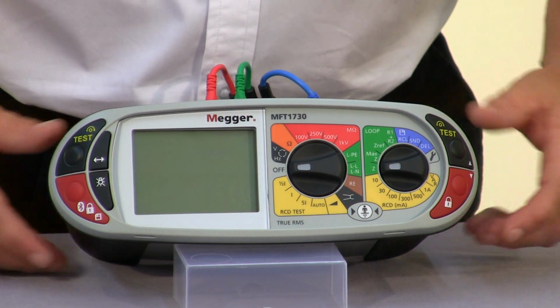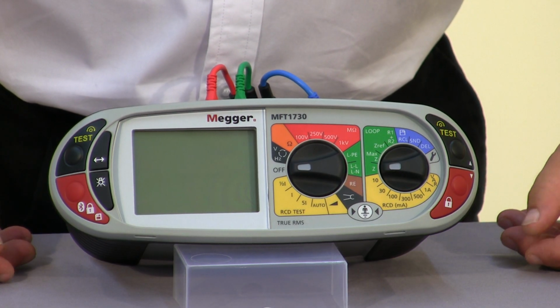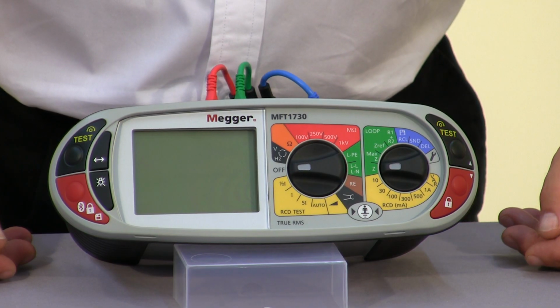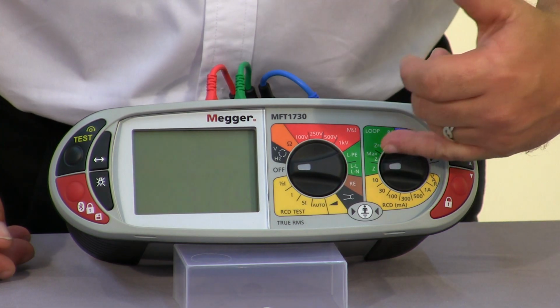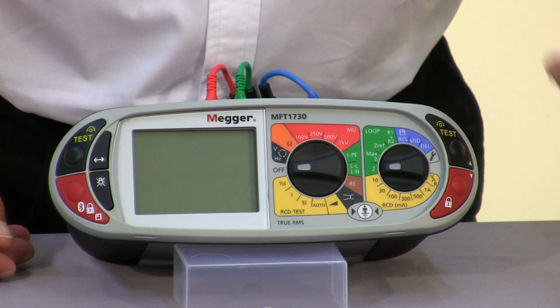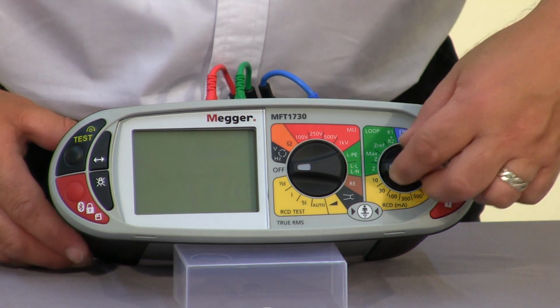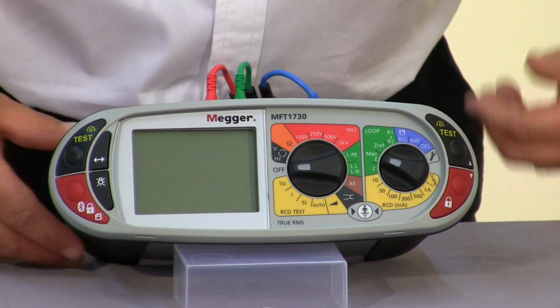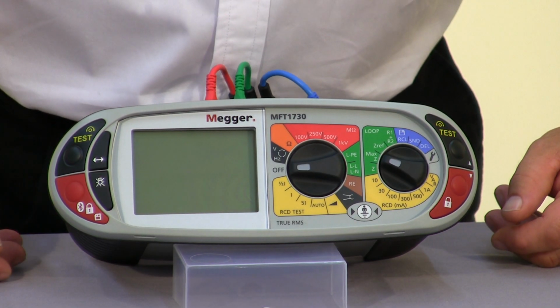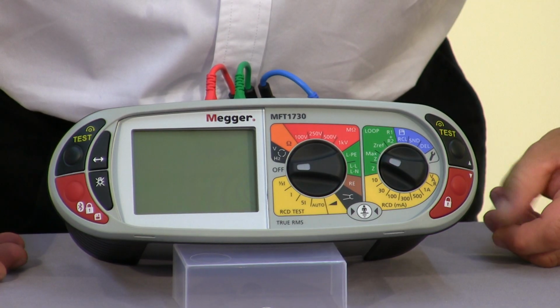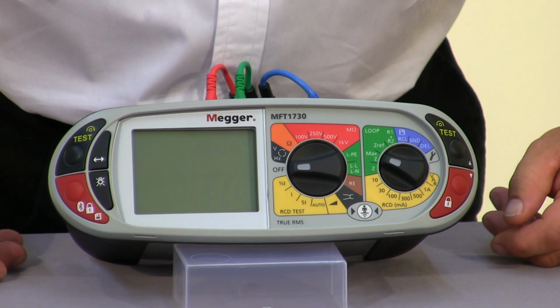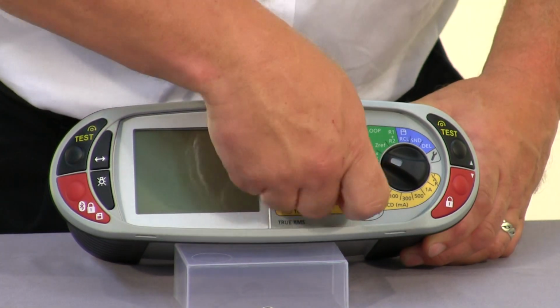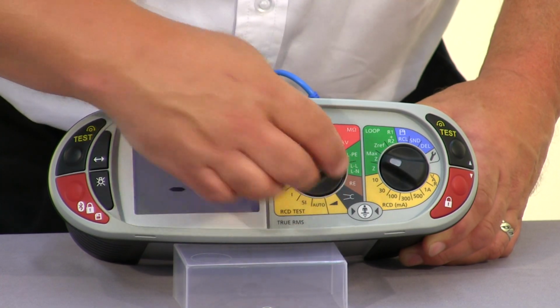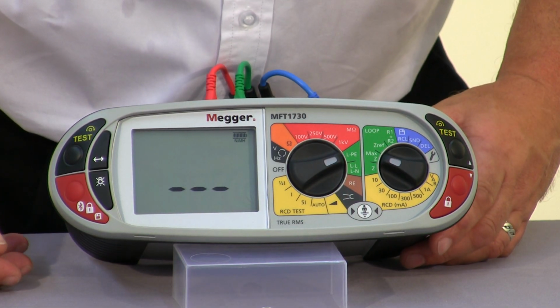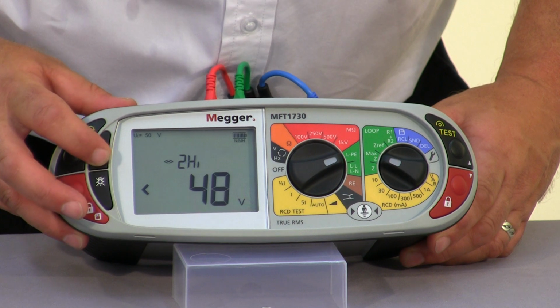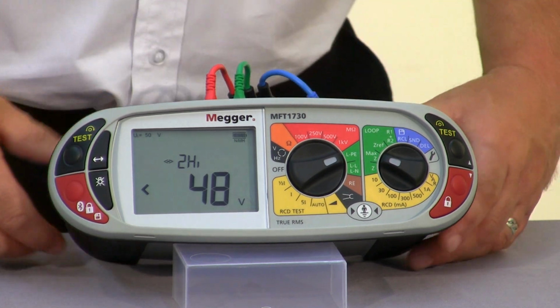Okay, so let's look at the other features that are available for loop impedance testing on the 1720 and the 1730. You'll see we have a ZMAX, a reference and an R1, R2 facility. Selecting the ZMAX first, this will allow us to carry out a sequence of tests whereby the highest reading is always returned on the upper of the two parameters on the display. So I'm just going to do a two-wire high current test. So we're simulating testing on an unprotected circuit.